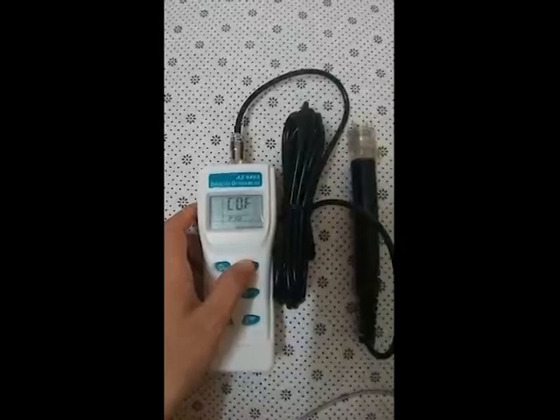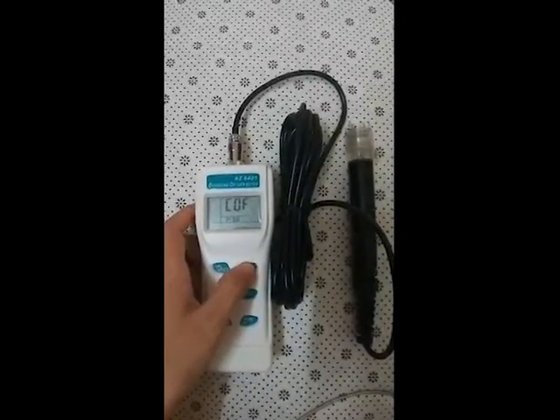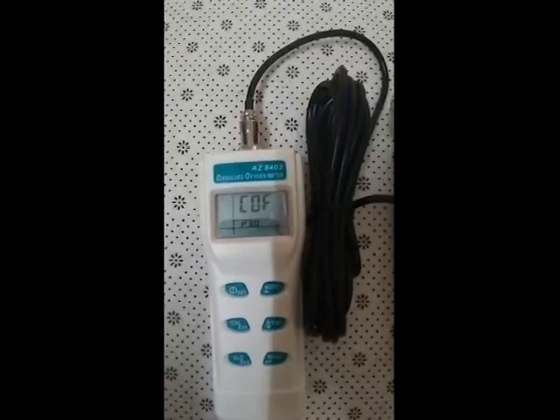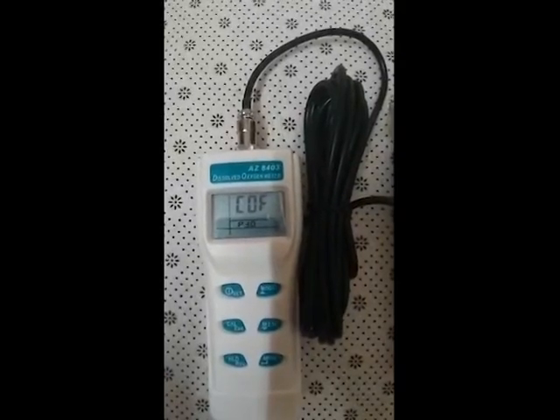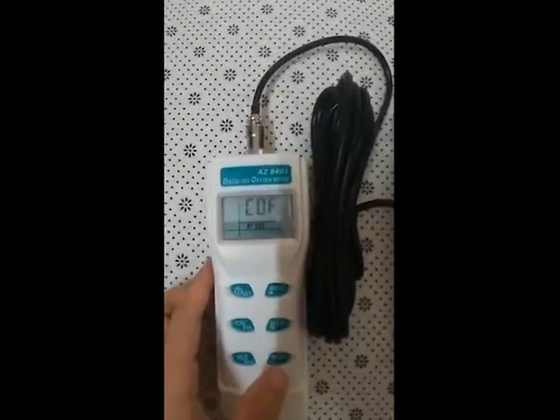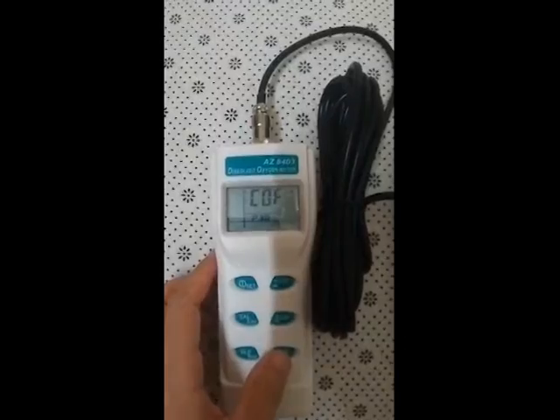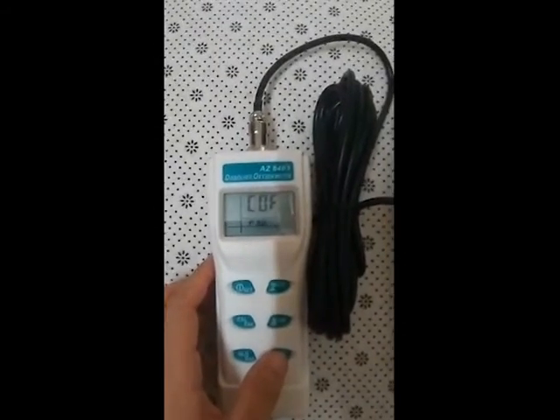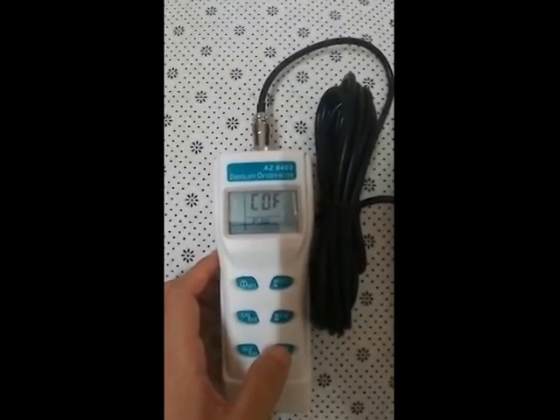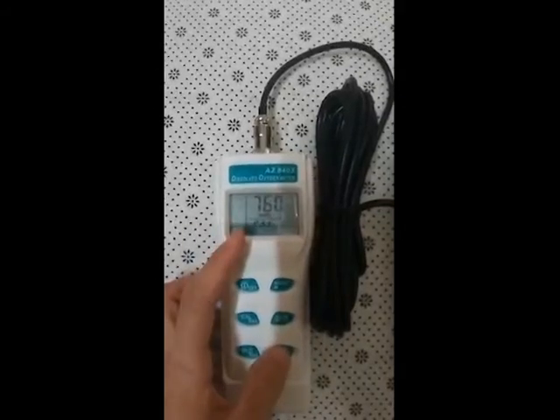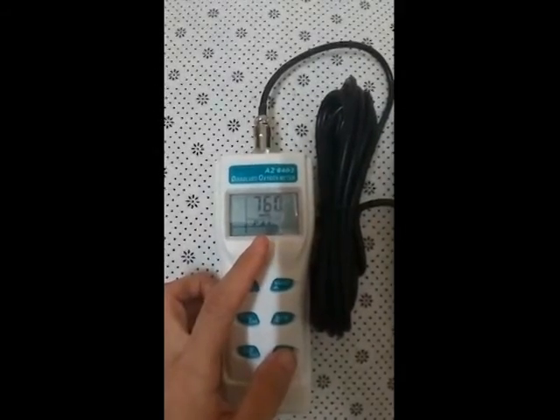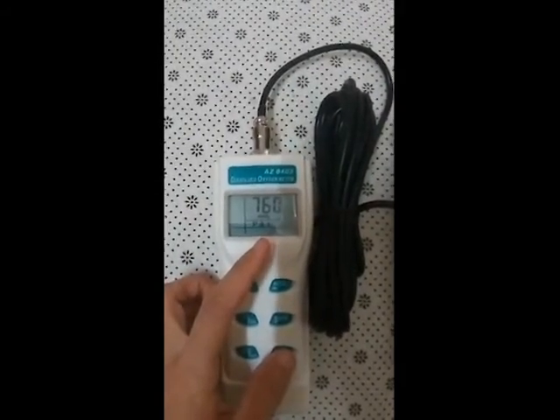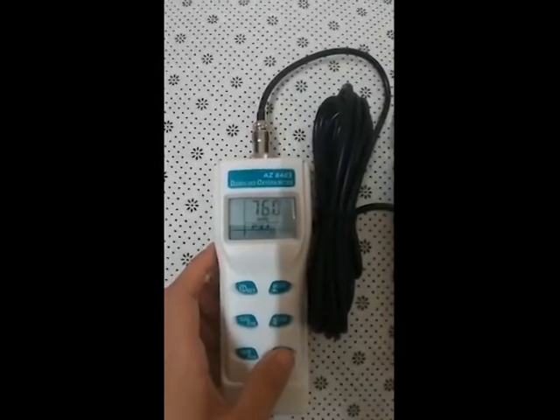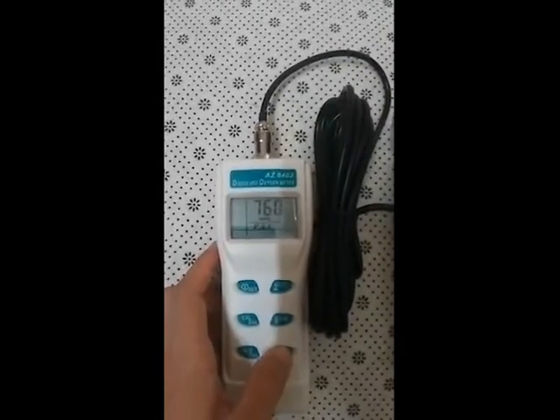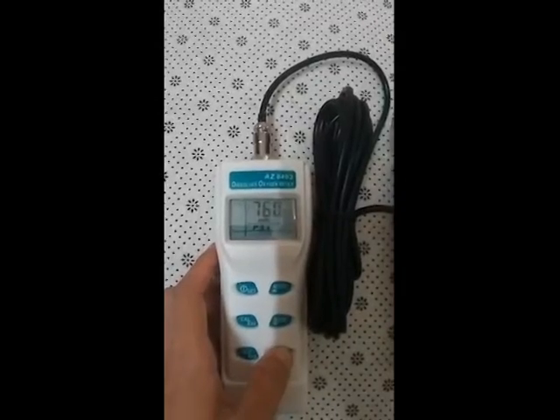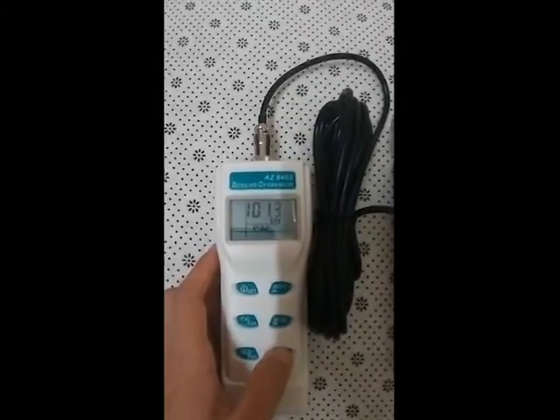P3.0 is about the pressure and the salinity coefficient. This one will be used when your water is not fresh water. It's like you have salt or seawater. Then you must enter this value. And if your altitude is not at sea level, you can refer to the table to set this pressure either in millimeter mercury, hectopascal, or kilopascal.